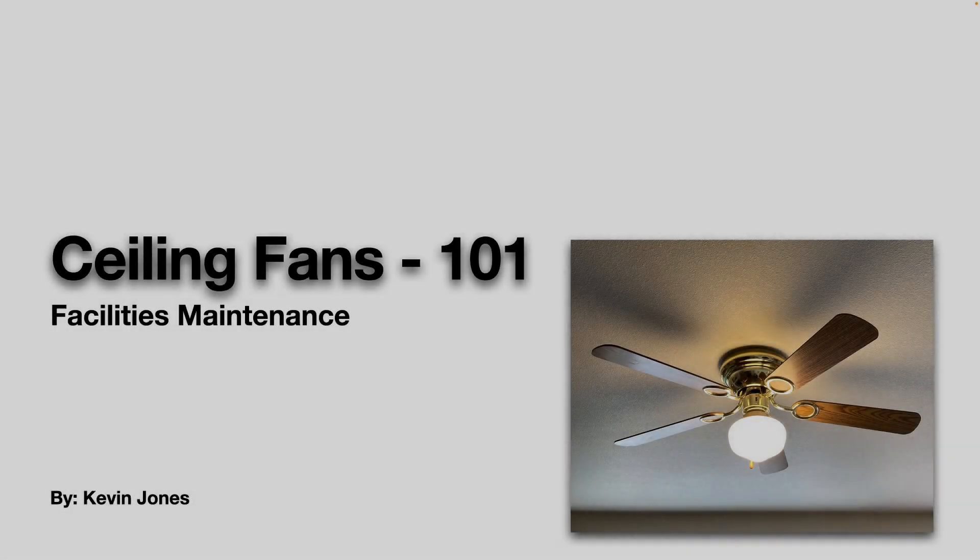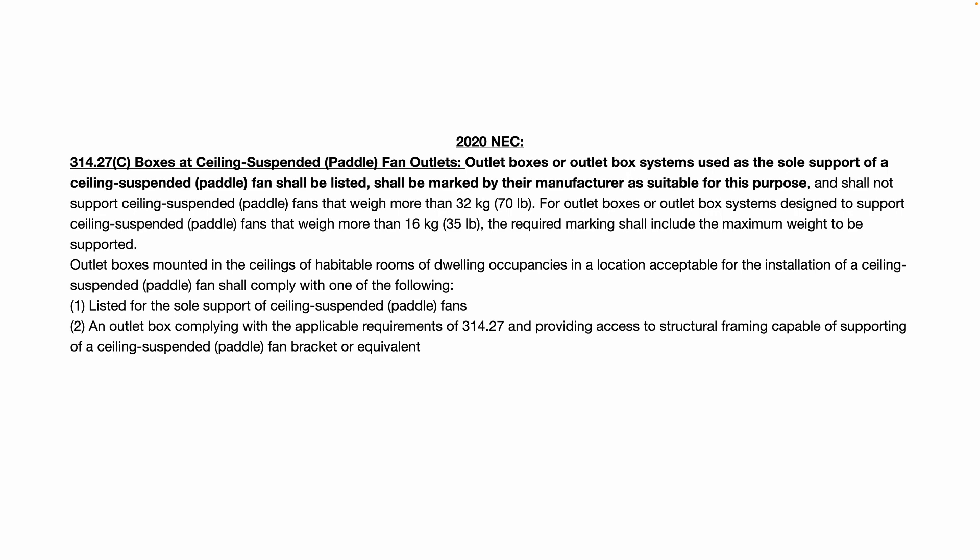Today we're talking about ceiling fans. According to the NEC — the National Electric Code — as of 2020, Section 314.27C is what talks about boxes at ceiling-suspended fan outlets. The important takeaway here is: outlet boxes or outlet box systems used as the sole support of a ceiling-suspended fan shall be listed and shall be marked by their manufacturer as suitable for this purpose.